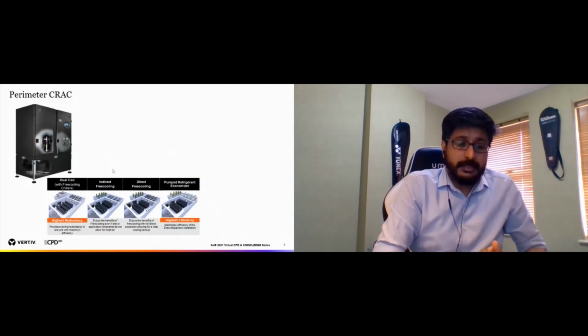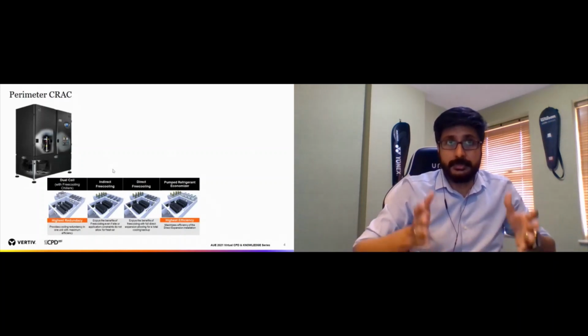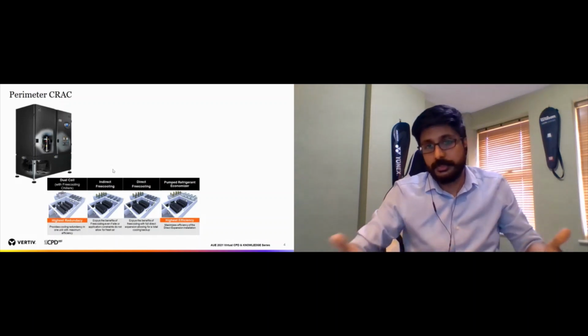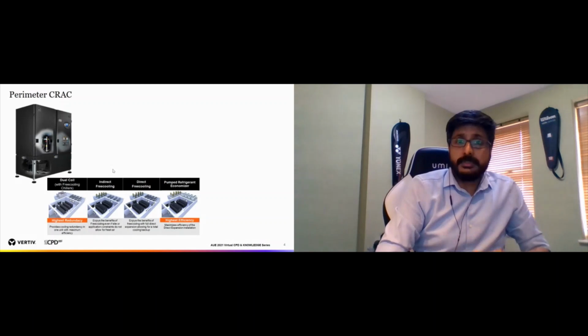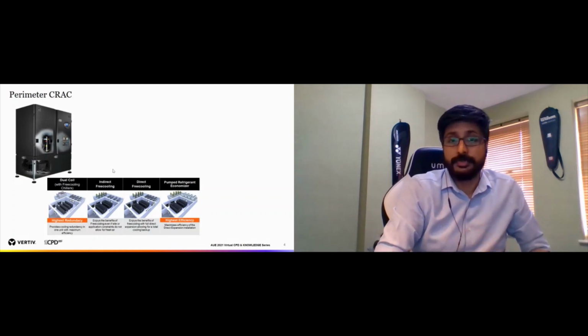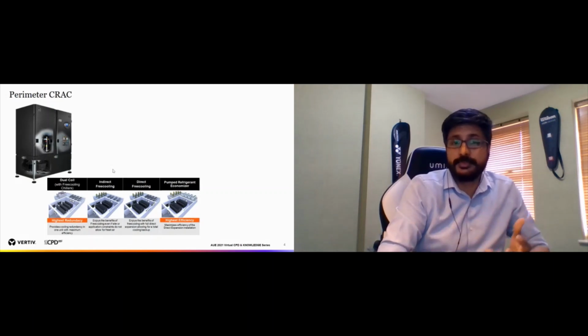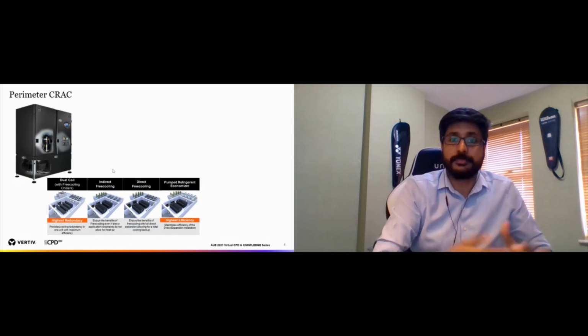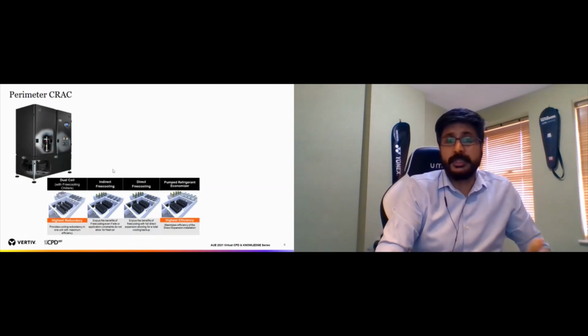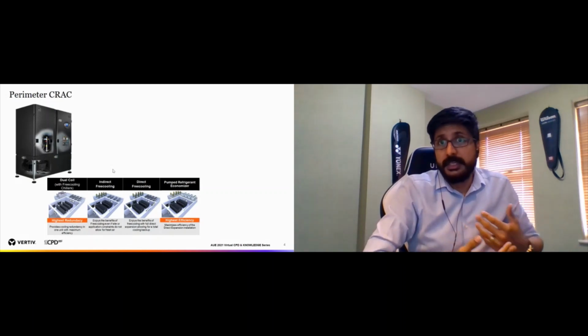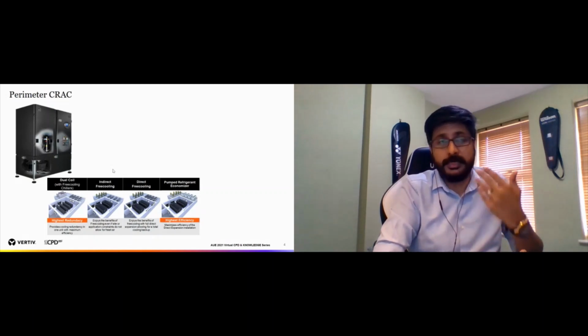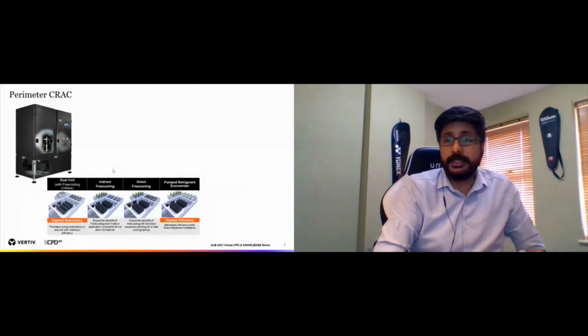Traditionally, we would be seeing around 10 kilowatts from a rack's point of view, but from a unit point of view, you can see up to 80 kilowatts. But recently there have been discussions and studies about chilled water, the amount of chilled water units, and the amount of water being used in a data center or in a cooling room. And that's when DX priority has come in again. So for that, we've extended the pumped refrigerant economizer system to even bigger sizes, up to 400 kilowatts of capacity. These 400 kilowatt systems can sit outside, and we don't need chilled water as such. The whole unit gets cooled by the DX expansion systems. You can avoid any piping and additional refrigerant inside the building, and it's a fully packaged DX system that you can place outside as well.